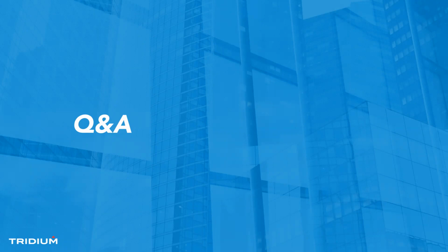The system database is only for a supervisor, so it's only licensed for supervisor platforms. But you can have intermediate JACEs that aren't running the system database, which can be the mid-tier hop that lets it route the information up from downstream stations.